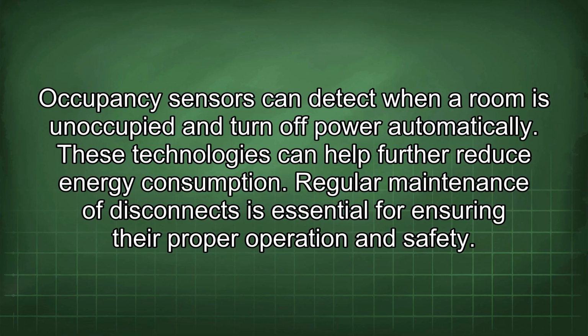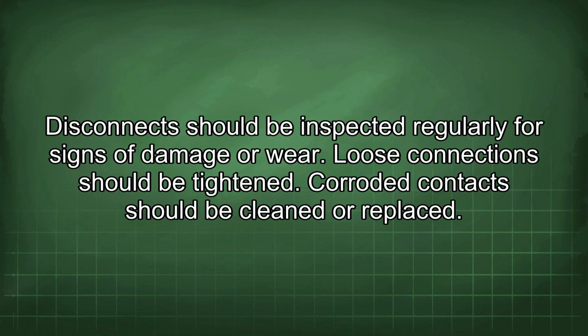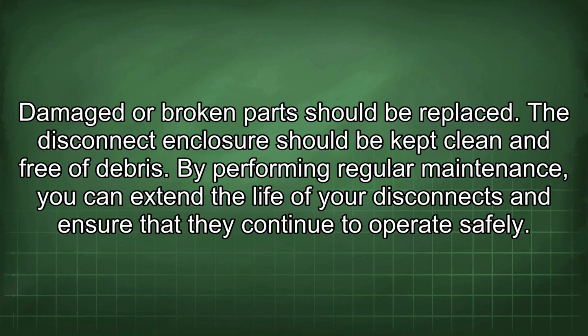Regular maintenance of disconnects is essential for ensuring their proper operation and safety. Disconnects should be inspected regularly for signs of damage or wear. Loose connections should be tightened. Corroded contacts should be cleaned or replaced. Damaged or broken parts should be replaced. The disconnect enclosure should be kept clean and free of debris. By performing regular maintenance, you can extend the life of your disconnects and ensure that they continue to operate safely.